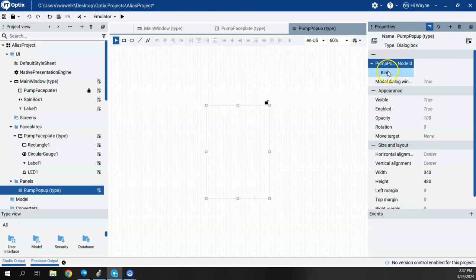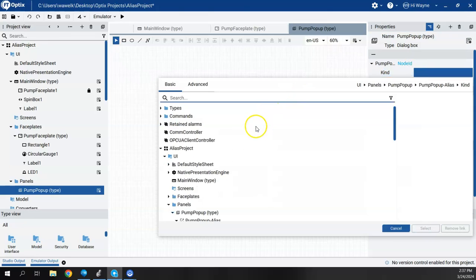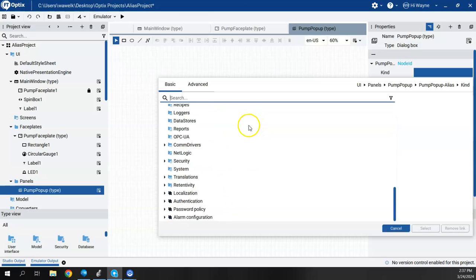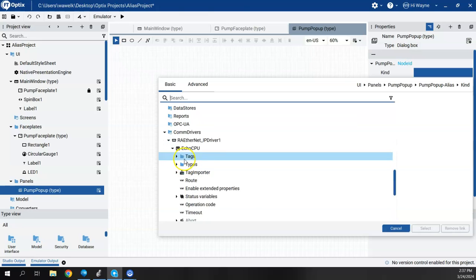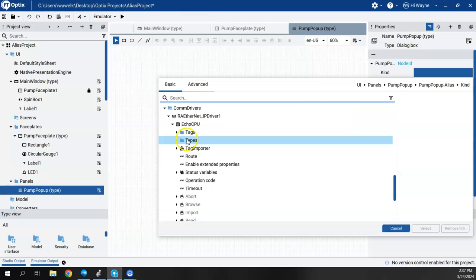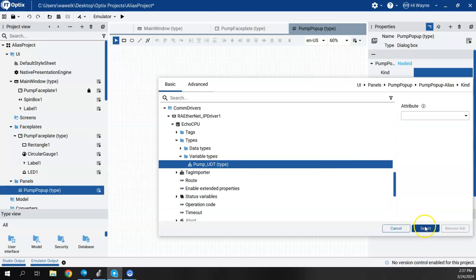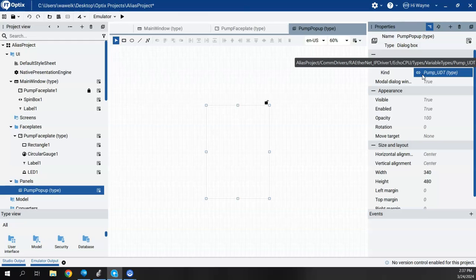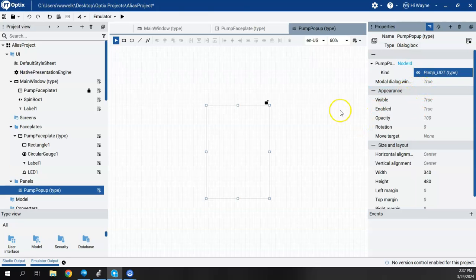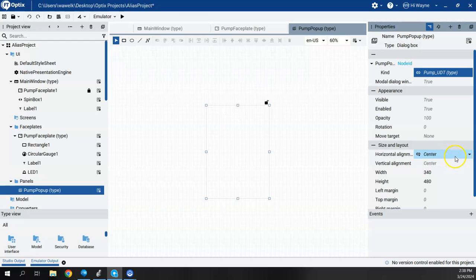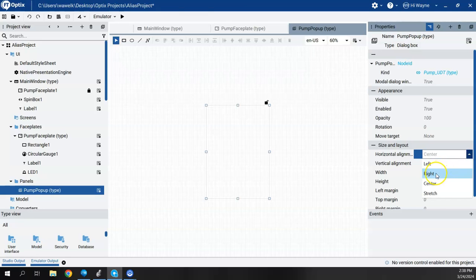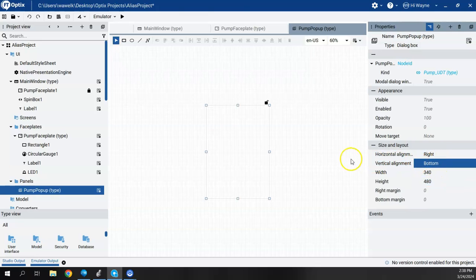Under kind, I'm going to do like I did in the previous video — I'll link the kind down to the UDT type underneath my Logix com driver. I'll go to types, variable types, and click on the pump UDT type in parentheses. That links it to that UDT type that I'll call on each time. For the dialog position, right now it will be centered both horizontally and vertically. I could also change the layout to align to bottom right for this application.